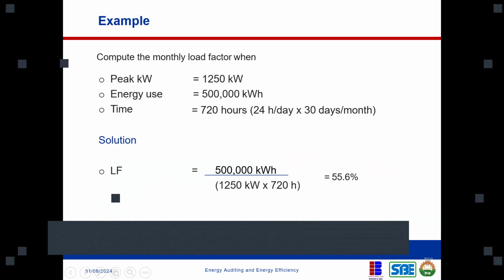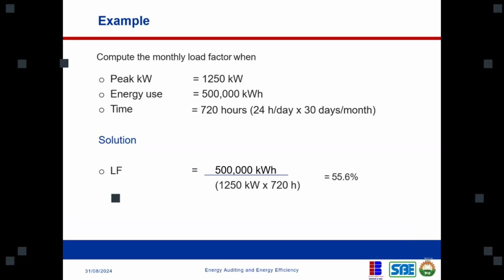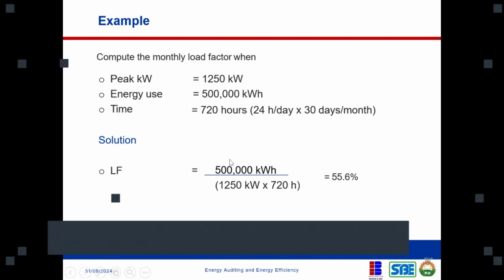So this is a typical example of peak demand and load factor. Compute the monthly load factor when peak demand is 1,250 kilowatts and energy use is 500,000 kilowatt hours. The time in that period is 720 hours, which is 24 hours per day times 30 days per month. That gives 720.